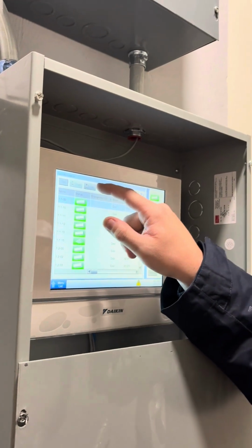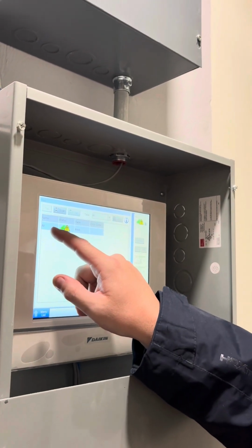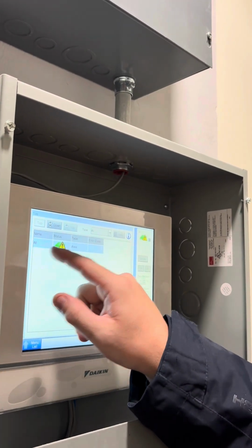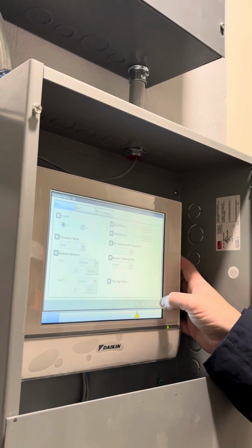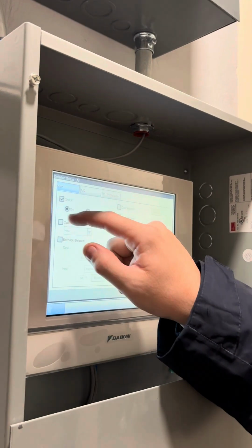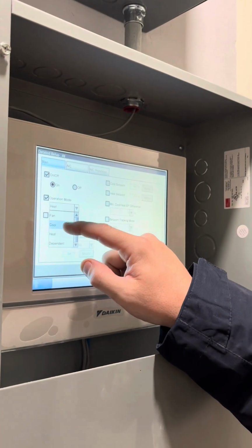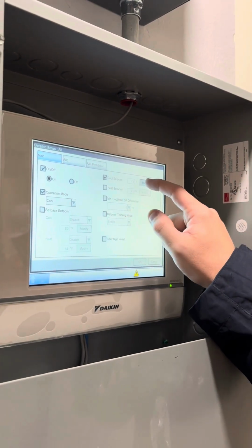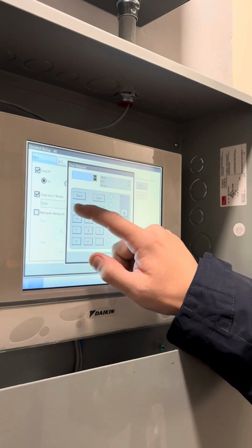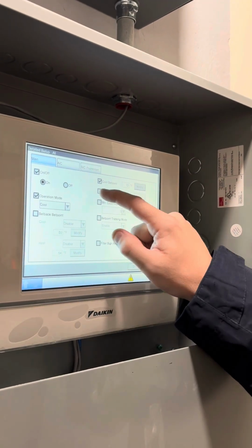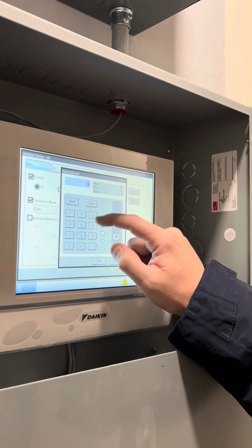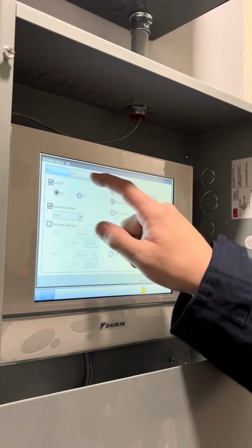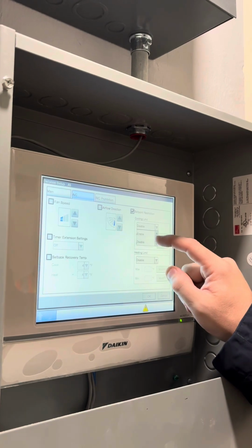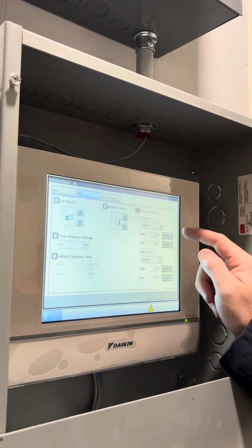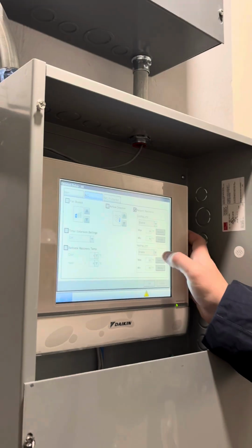If you hit the top button, that brings you to the screen showing all of them, where you can broadcast whatever you want to all of them. So if you wanted to say, hey, I want all of them on, operating and cooling, with my cooling set point at 72 and my heating set point at 69, you could do that. Or go to the AC settings and restrict how high or low they can go.